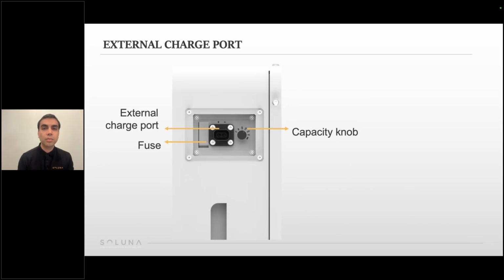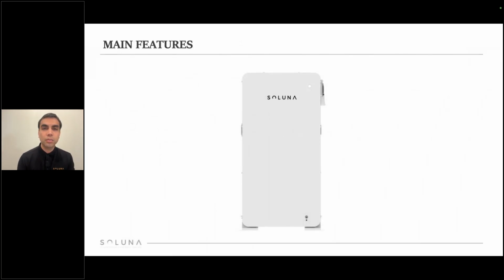The external charge port, you have the external charge port on the side, and now the new versions have the capacity knob, which, for example, if you have a 15K and it went over this charge, then you can turn the knob down to 10K so that it can wake up the battery, and we can monitor what is going on in the battery and be able to troubleshoot. It has a fuse, and this is for protection. Of course, it's a lithium battery.